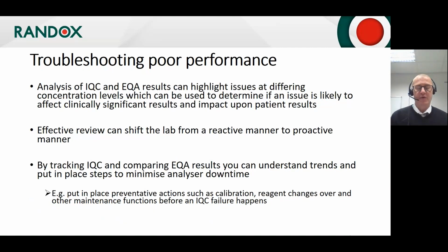So the analysis of both IQC and EQA can highlight issues at different concentration levels. This can be used to determine if an issue is likely to affect clinically significant results and impact upon patients. So really what we're saying here is that if you can highlight that you've got a problem at the high end of an assay, then if your clinically significant target is at the high end, then obviously you've got a problem.